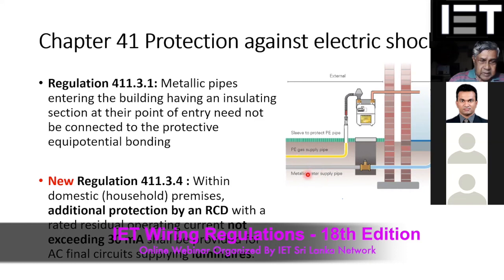Because of that, what they said is if you are connecting this pipeline through a non-metallic pipe, then you don't want to worry about this part. But if it is continuing as a metallic pipe, then you have to connect to the equipotential bonding. So that is one of the major changes in the regulation.